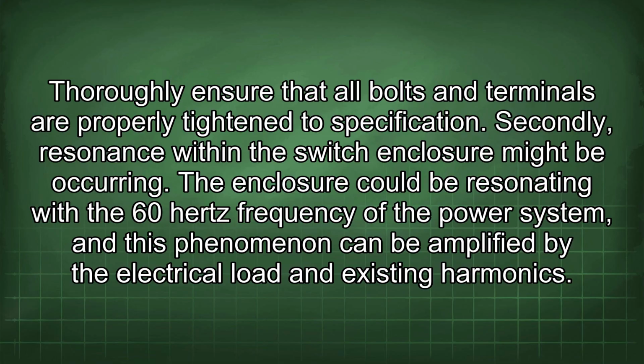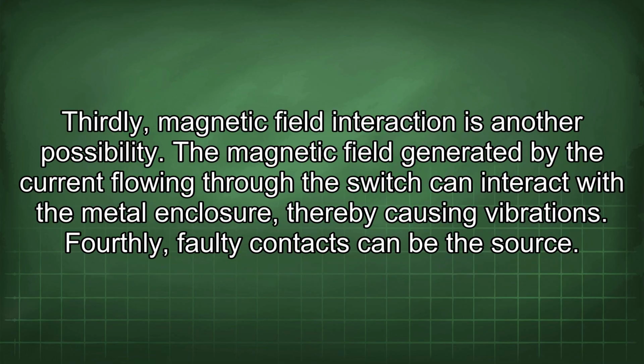Secondly, resonance within the switch enclosure might be occurring. The enclosure could be resonating with the 60 Hz frequency of the power system, and this phenomenon can be amplified by the electrical load and existing harmonics. Thirdly, magnetic field interaction is another possibility. The magnetic field generated by the current flowing through the switch can interact with the metal enclosure, thereby causing vibrations.